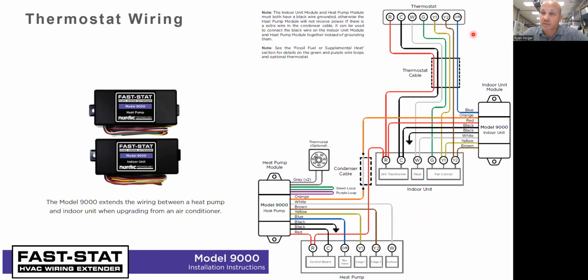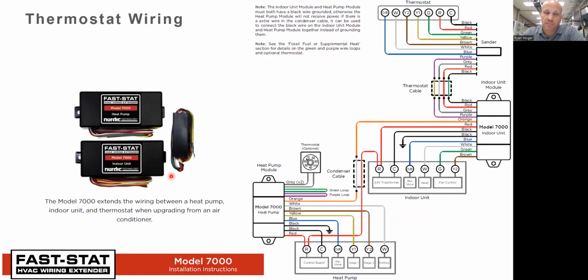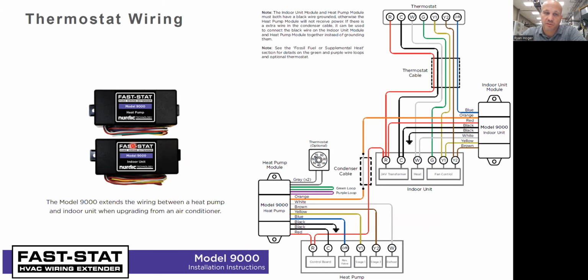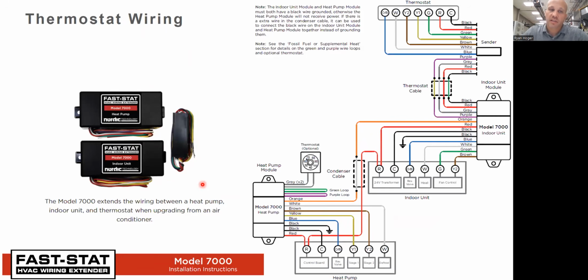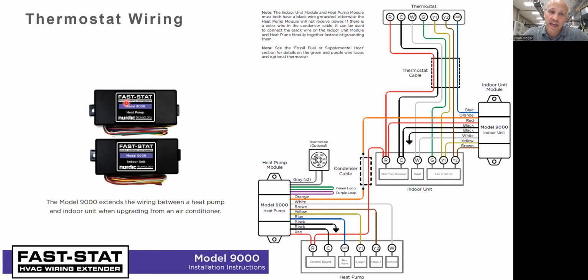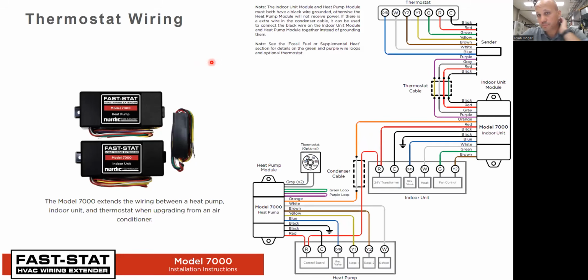So what ends up happening with one of these, let's use this one as an example. This one's a less expensive, simpler version. This one's the more complicated one. If you understand the more complicated one, you understand both. By the way, the 7,000 for this brand does more stuff than the 9,000. And from a model number standpoint, that bothers me. So just know that. Here's my thermostat up here. Here's my indoor unit, air handler, or furnace, whatever I got. And then here's my outdoor heat pump over here.